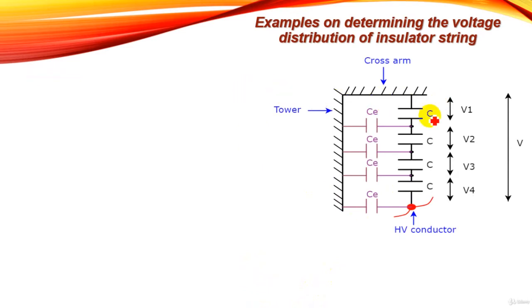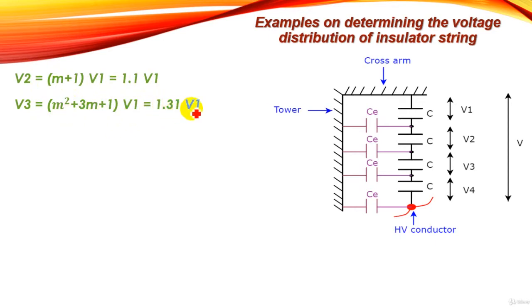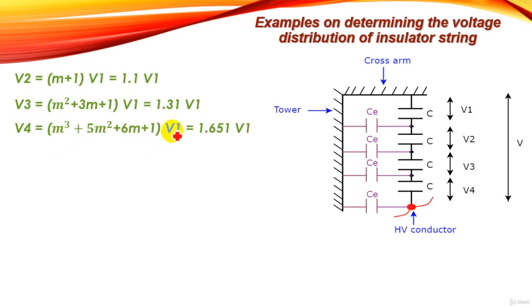Now the voltage distribution over each unit. We have: V2 equals (m + 1)·V1, so V2 equals 1.1·V1. V3 equals (m² + 3m + 1)·V1, so V3 equals 1.31·V1. And V4 equals (m³ + 5m² + 6m + 1)·V1, so V4 equals 1.651·V1.